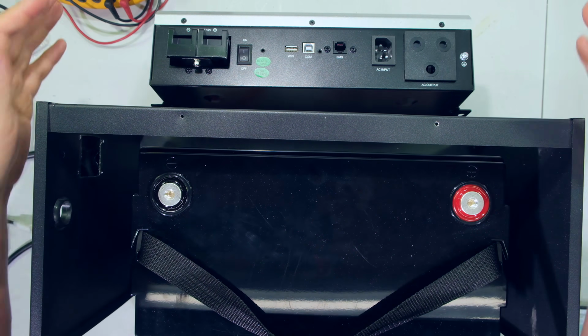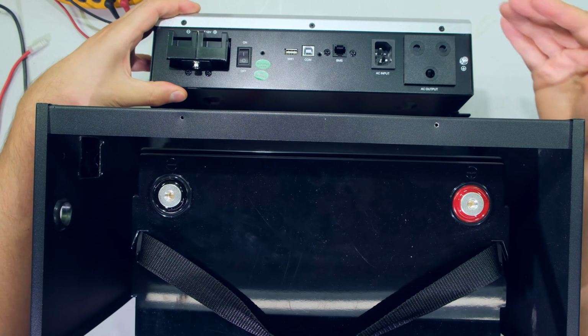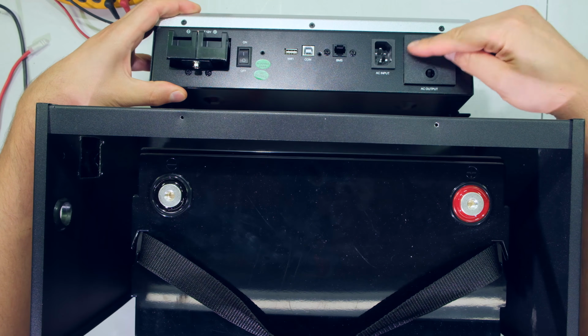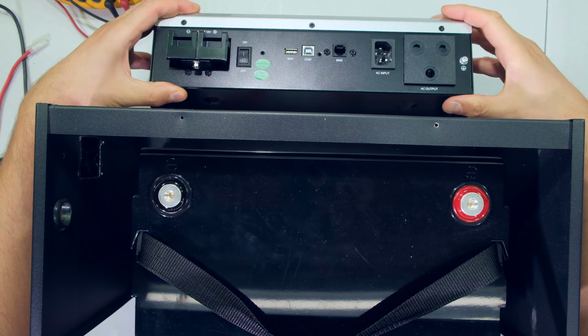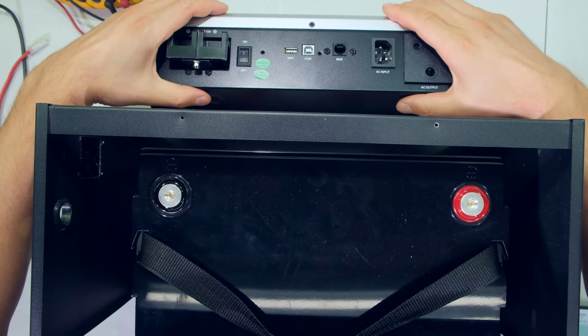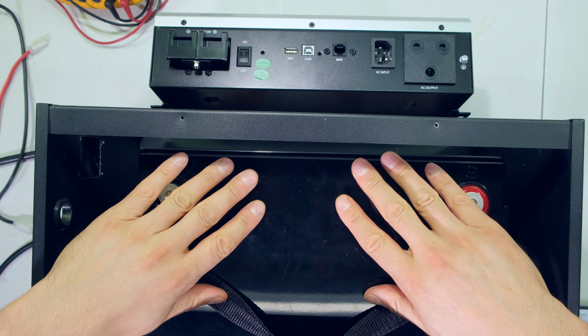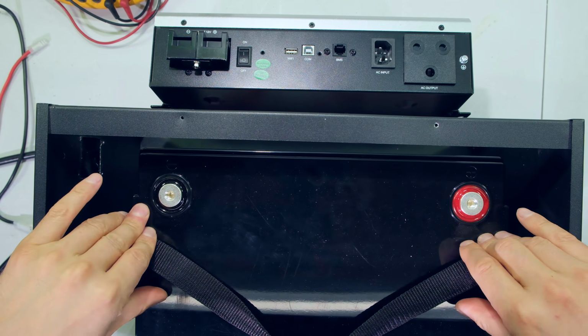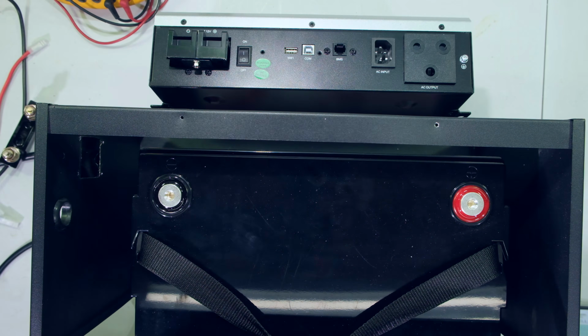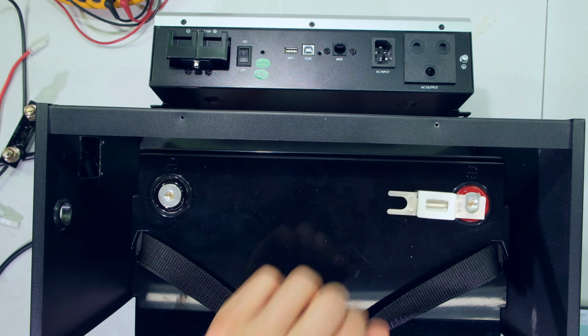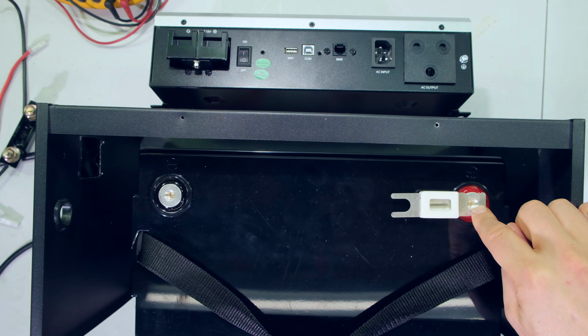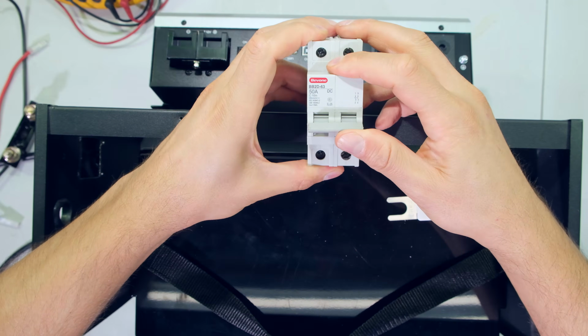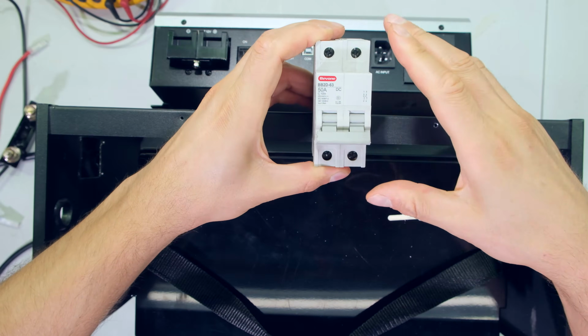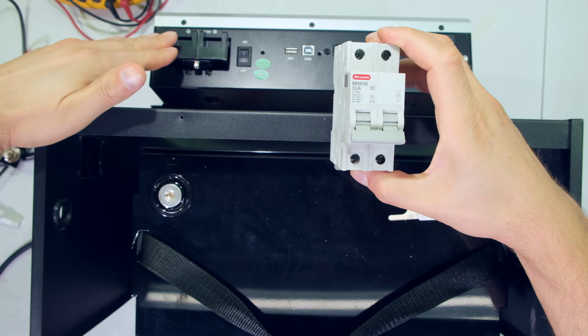However, I need to make sure that if there's a fault inside here, maybe somebody spills water on it, or maybe somebody connected a microwave oven, whatever, if there's a fault inside here, I need to be able to protect this battery from an overload condition or a fault condition. So that means I'm going to need to use a fuse. There's a fuse here right at the battery, or I can also use this DC circuit breaker in between the battery and the inverter.